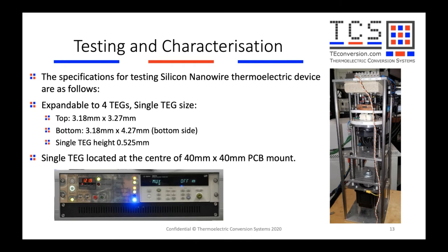We've developed various testers for different companies, different materials and different universities. So really down from the very small 3mm by 3mm size of TEG - this was for a silicon nanowire thermoelectric device. You can see in the image, we've got a stepper motor that provides pressure compensation and control over the applied pressure and the clamping to the thermoelectric device, and we've also got a heater for the hot side.